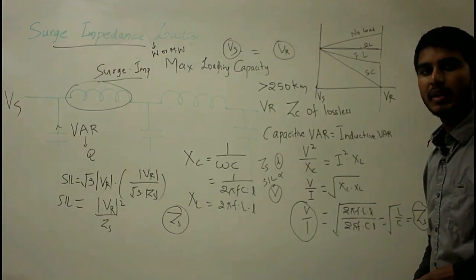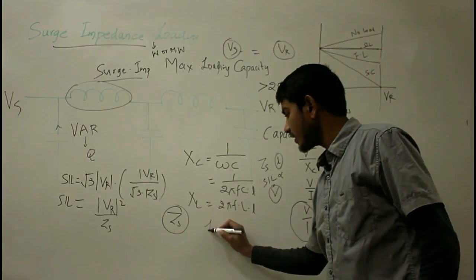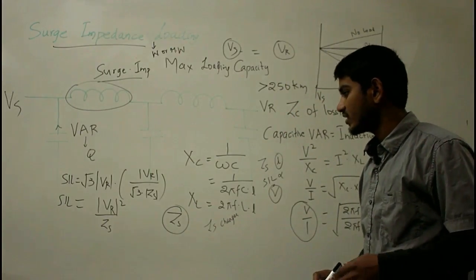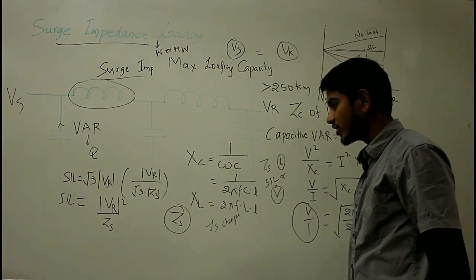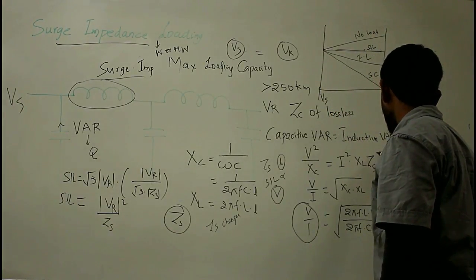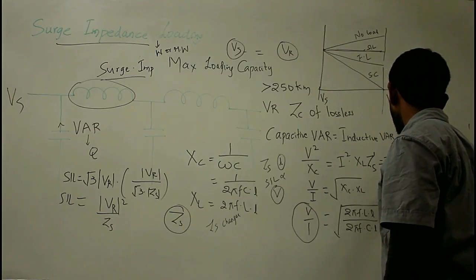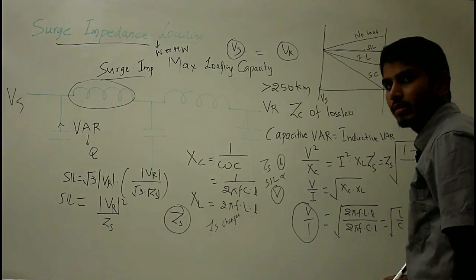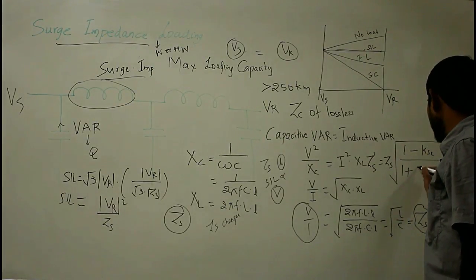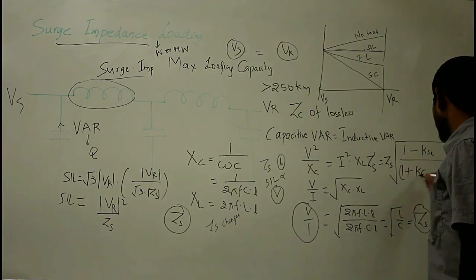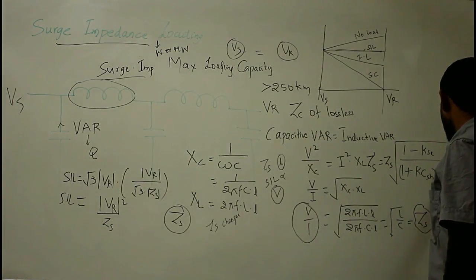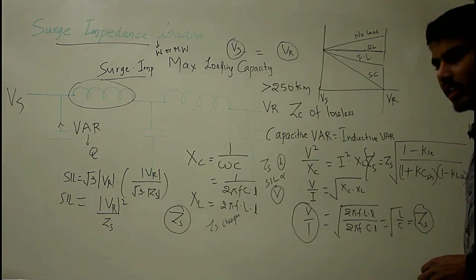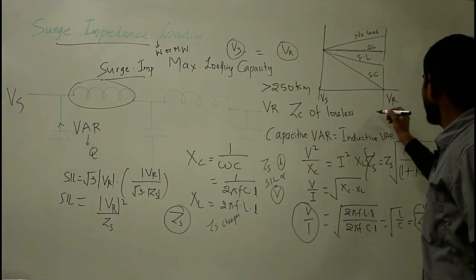When we go to a compensated line, the value of ZS changes. For a compensated line, the new value is: ZS' = ZS × √((1 − ksc) / ((1 + kch) × (1 − klsh))). This is the new value of ZS' for a compensated line.